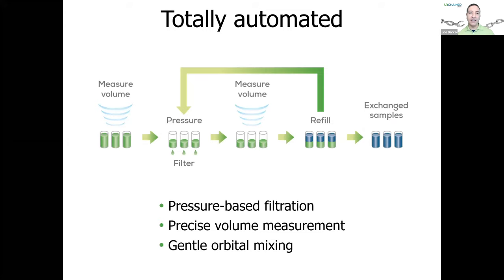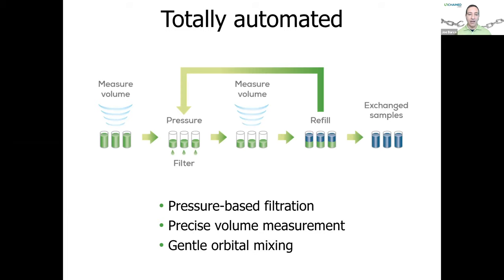We fully automated what you would normally have to do manually. If you think about how you normally do buffer exchange by centrifugation filters — you add a volume, check the volume, put it in the centrifuge, wait, come back, look at what volume has been removed, then add new buffer and repeat. What we automate is the volume measurement process and that cycle. Instead of centrifugation, we use a pressure chamber pressurized to about 60 PSI with gentle orbital mixing occurring throughout.